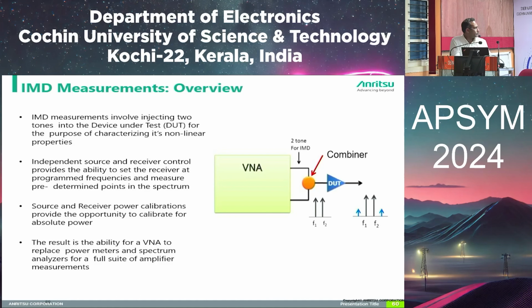We have individual sources, and we will do the calibration at the end of this cable. We will do the source calibration at port 1 and port 2, and we will do the receiver calibration using a path, and after that we will connect a combiner internally and it will be fed to the DUT. So any doubt in IMD?